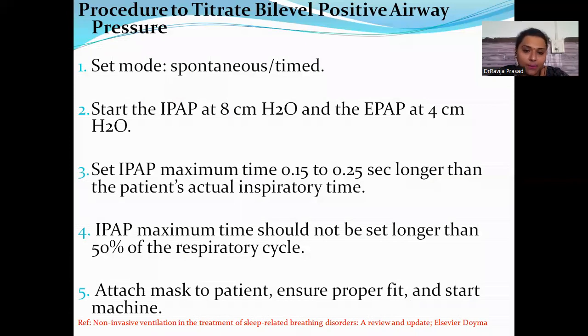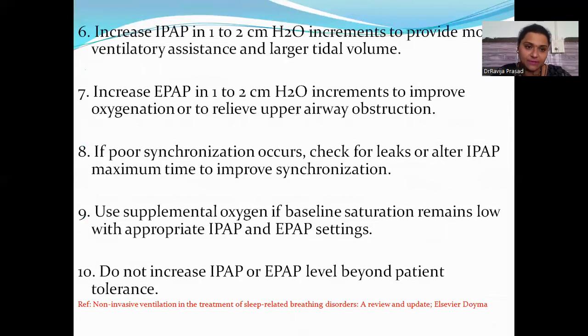Then set the IPAP maximum time of 0.15 to 0.25 seconds, longer than the patient's actual inspiratory time. The IPAP maximum time should not be set longer than 50% of the respiratory cycle. Then attach the mask to the patient, ensure proper fit, and start the machine.